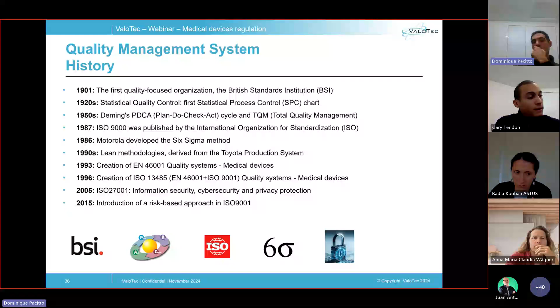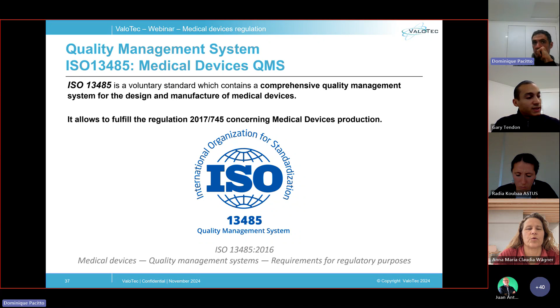Okay, so now let's focus on the core of this presentation: the ISO 13485 standard. This standard defines the requirements of a quality management system for medical devices. A quality management system for medical devices refers to the systems and processes put in place to ensure that medical devices meet regulatory requirements. The standard includes requirements for managing the entire life cycle of a medical device, from design and development to manufacturing, distribution, and even post-market surveillance. It allows you to fulfill the European regulation concerning medical device production. It can be applied to anything from a one-person company to a multinational company with thousands of employees. And you have to know that equivalent standards exist for other professional sectors.